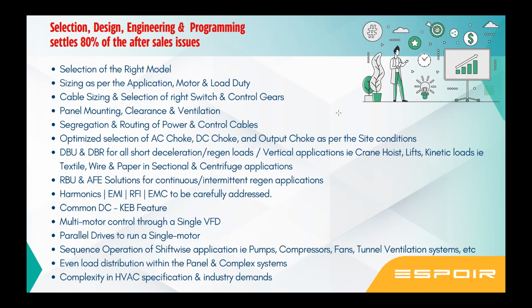There is something called multi-motor control through a single VFD. Motors are run by one VFD, the LTs. You need to have a particular motor-specific OLR connected in the output. Your selection of a VFD should be higher than the sum of all the motors connected on the output. One aspect of a multiple-motor, single-drive configuration is that all motors will run at the same time, at the same speed and the same sequence. So if you need an independent sequence, then you cannot go for a single VFD multi-motor configuration. Now every motor has a different overload protection.